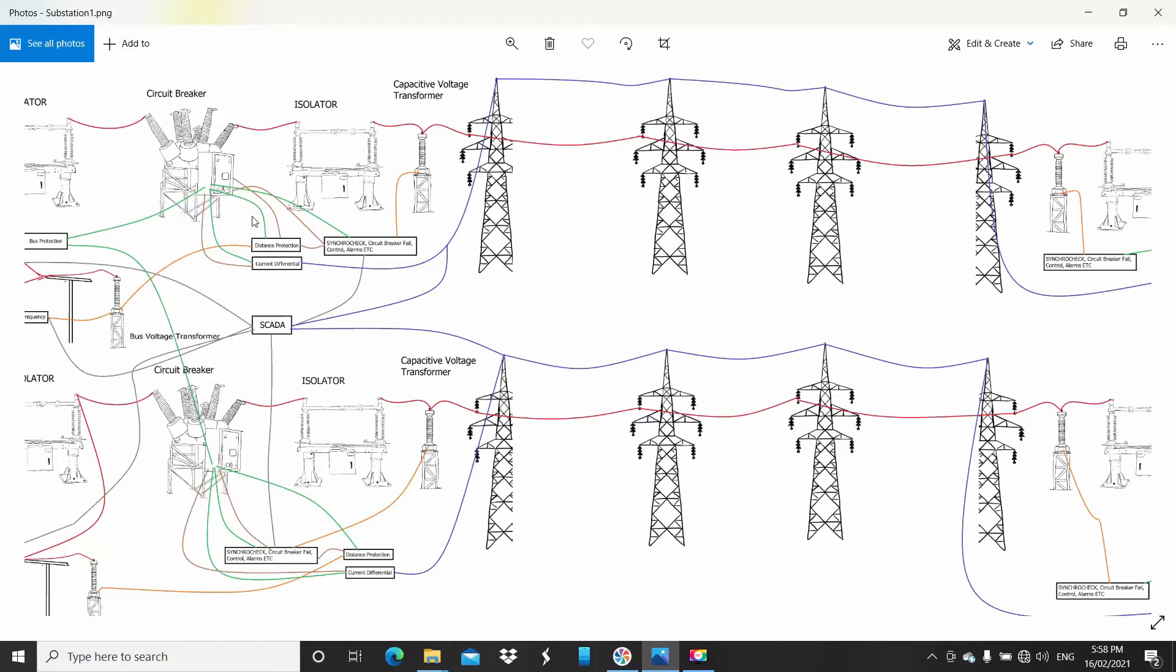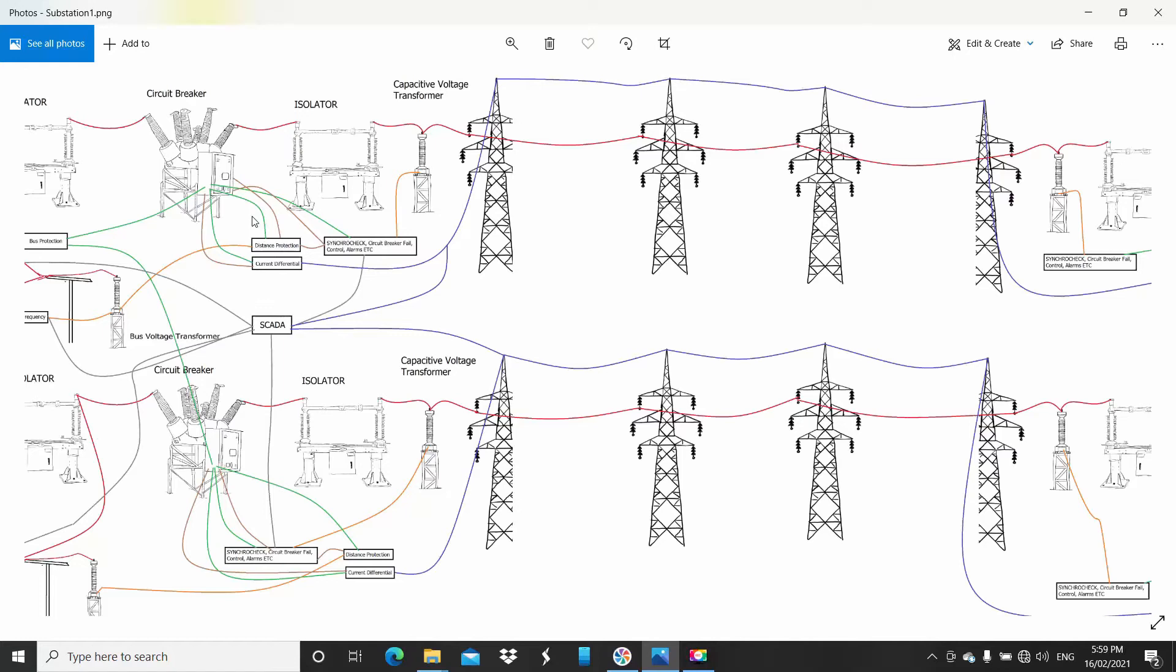What you find in impedance relays is you have things called zones. For example, the first zone is often 80% of the line. Having multiple zones allows for discrimination in tripping, preventing everything from the energy source—the generator—from tripping all the way along. We don't want that. We want the fault to be a small location as possible. We want to trip the least amount of things as possible to contain the fault. I'll have a future video on impedance relays that will cover this in more depth because it's quite a big complex subject. I'll try and make more videos in depth about each one.